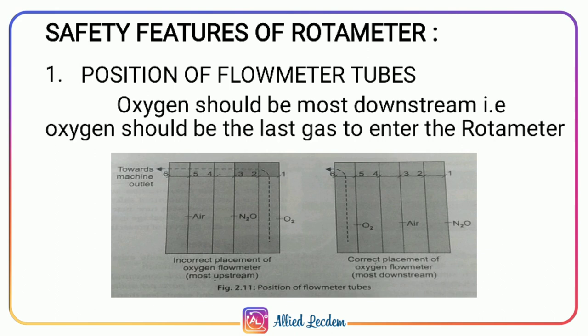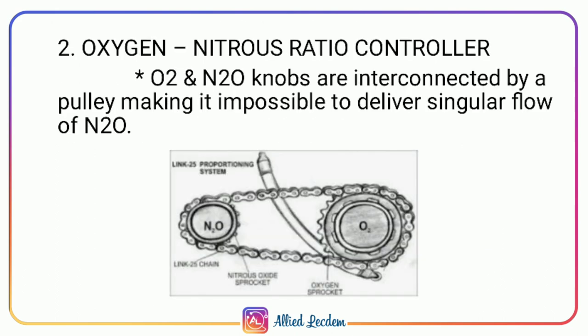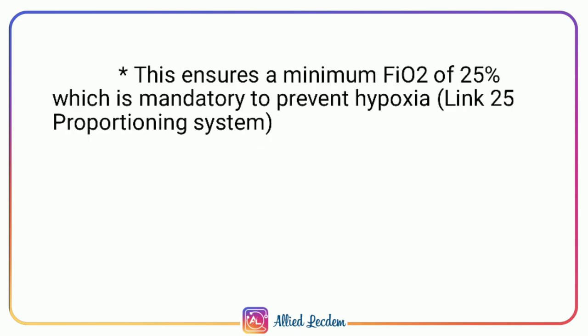Nitrous oxide, when administered alone without oxygen, is toxic to the patient causing serious complications. Therefore, the oxygen and nitrous oxide knobs are interconnected by a pulley, making it impossible to deliver a singular flow of nitrous oxide. This system is called the Link-25 proportioning system. When nitrous oxide is turned, the pulley automatically rotates the oxygen knob, ensuring a minimum fraction of inspired oxygen of 25%, which is mandatory to prevent hypoxia.